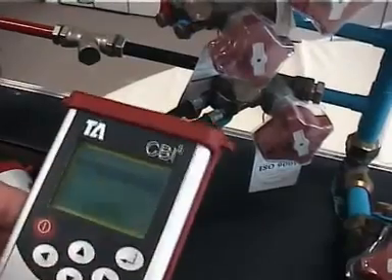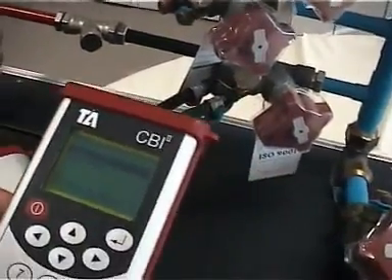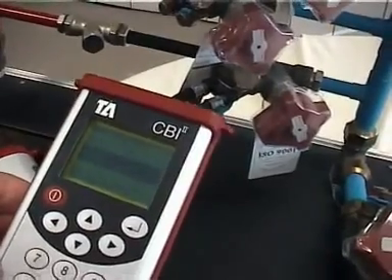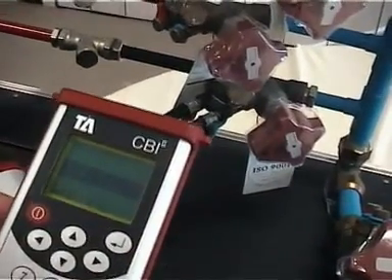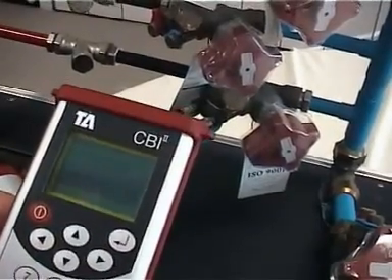It asks us for the type of valve, which is a 1514, which we programmed into what we chose before. That is correct. We can change that information just now. If we wanted to, we don't. Our desired flow rate is what we've chosen before from the engineer, 0.06. So we agree with that. Hit enter.